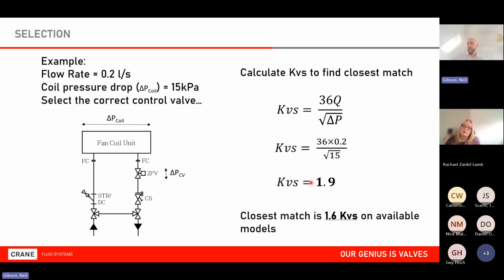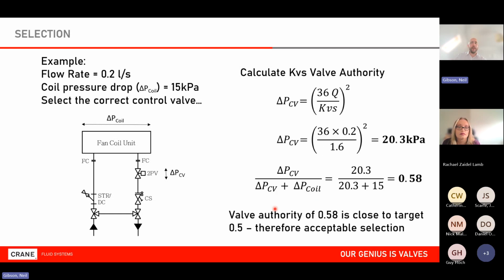That does not exist. There is no valve with a 1.9 KVS. So what do we do? We find the closest match, in this example 1.6. I then have to reverse the calculation. Now, this is all built within Excel usually, and it can be automated to a certain degree, but I still have to do it. So I didn't quite achieve 15 kPa based on my KVS of 1.6. I've achieved 20. So my valve authority isn't quite 0.5, it's 0.58. The key takeaway here is that there's always a compromise when selecting 2-port valves. They're never perfect. And I have to complete this exercise on every single one.